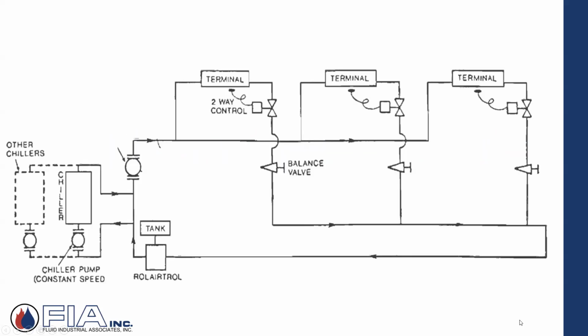So as systems grew, these are some of the pictures I'm going to show right now in this PowerPoint, out of some of the TEH manuals that you guys received, both in the manual and in the Dropbox on the PDF version. What they're saying here is I have a chiller plant, and then I have some closely spaced tees, relatively speaking. I have primary, secondary piping over here, where the chillers are inserted, if you will, into the distribution system. So I have a secondary pump that's now feeding terminal units. And these terminal units are controlled, in this case, by two-way valves.